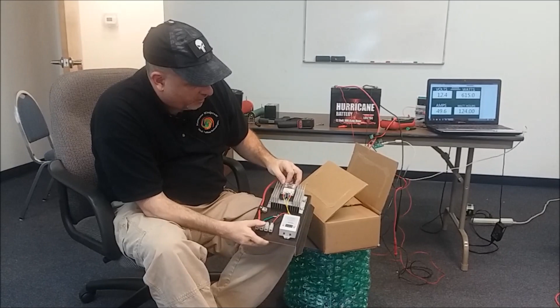I just don't like mechanical relays. I've seen too much stuff where they get stuck open or stuck closed, and it will ruin your battery one way or another. I'm going to do a demonstration another time showing how you need to match your diversion loads correctly with your batteries. If you put too much diversion load and this thing opens up, it's going to knock the hell out of your battery real quick - not good for the battery. But everything is a tool, and it has a time and place.